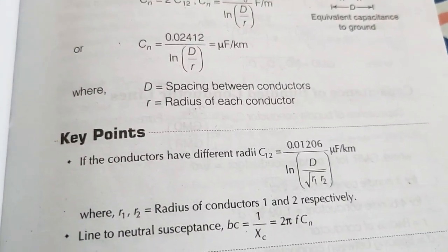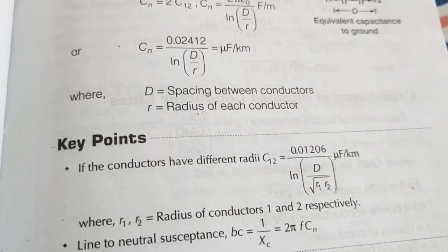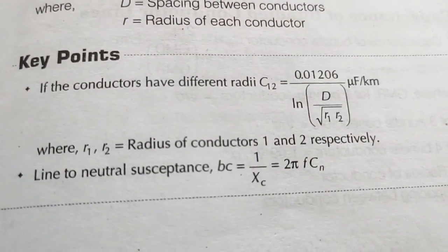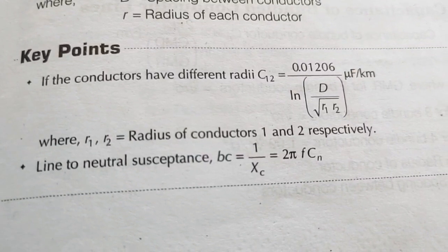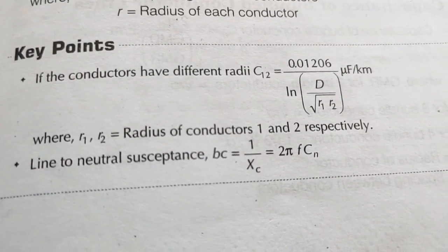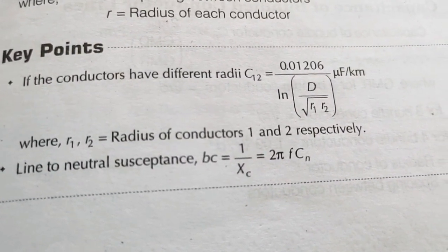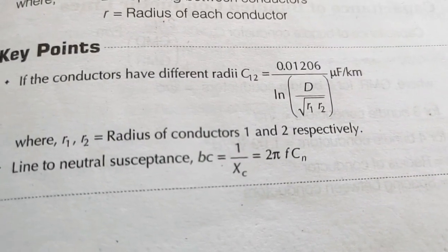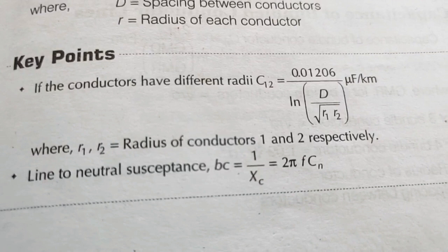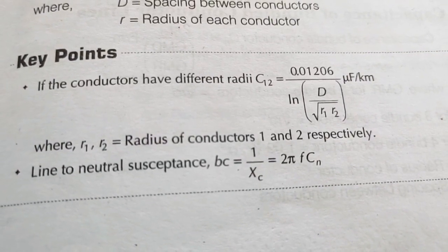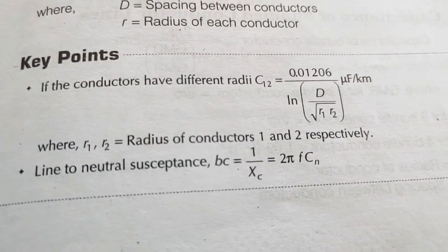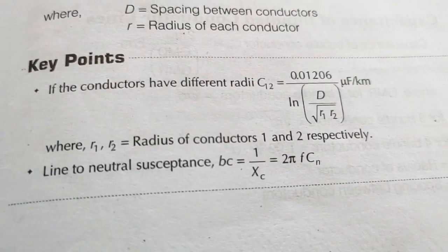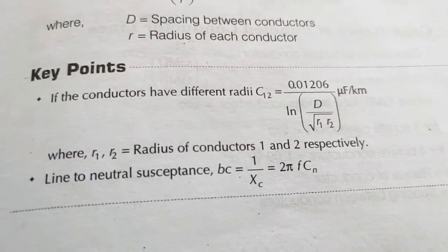Here D is the spacing between conductors and r is the radius of each conductor. If the conductors have different radii, C12 equals 0.01206 divided by ln(D / square root of r1·r2) microfarads per kilometer, where r1 and r2 are the radii of conductors 1 and 2 respectively. Line-to-neutral susceptance Bc equals 1/Xc, that is 2 pi f times Cn.